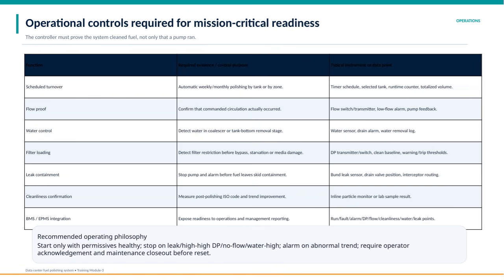Flow proof is about confirming that the commanded circulation actually occurred, which is verified by flow switches, low flow alarms, and pump feedback signals. This ensures that fuel is actively moving through the system. Water control is critical since water contamination can cause severe issues. Sensors detect water presence in coalescers or at the tank bottom, triggering alarms and logging water removal actions. Filter loading is monitored to detect restrictions before any bypass or damage happens.